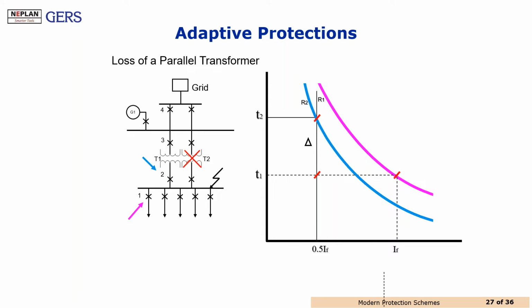Why? Because in this case, we will get a new fault current, and that fault current will be the same between relay 1 and relay 2. Everything comes here. But also relay number 1 will see that the current is reduced, but number 2 will see that the current has increased. Based on that, the new setting for the operation time of relay number 2 should ensure the time dial that will provide the new setting of the relay.